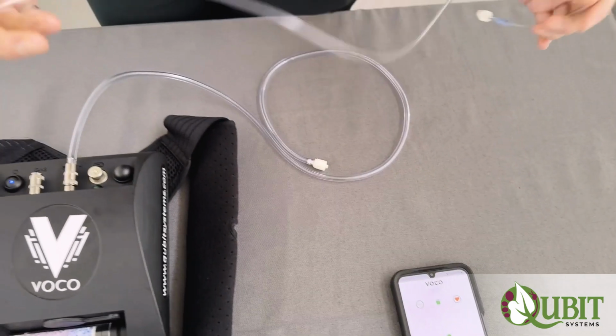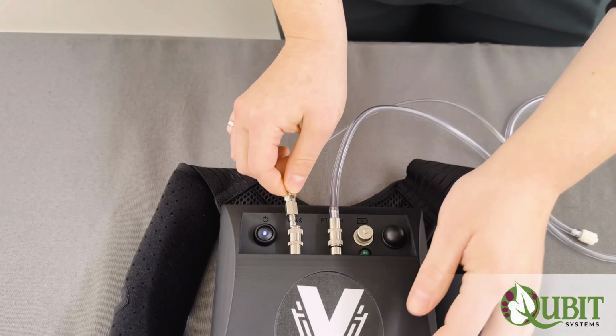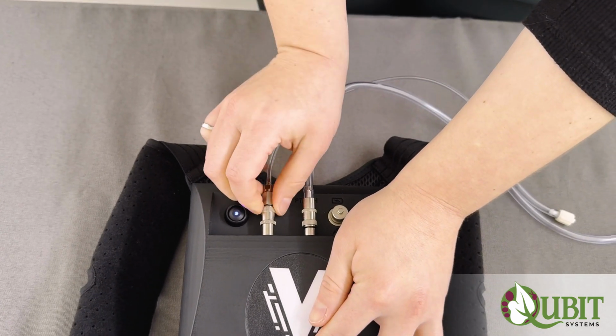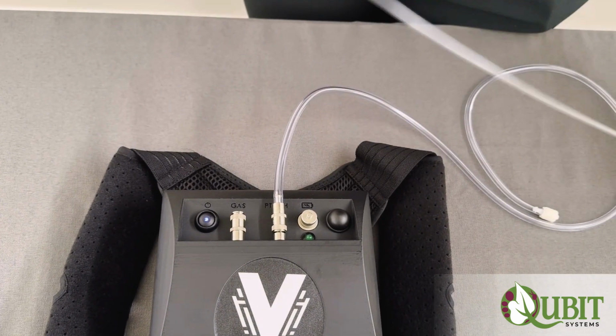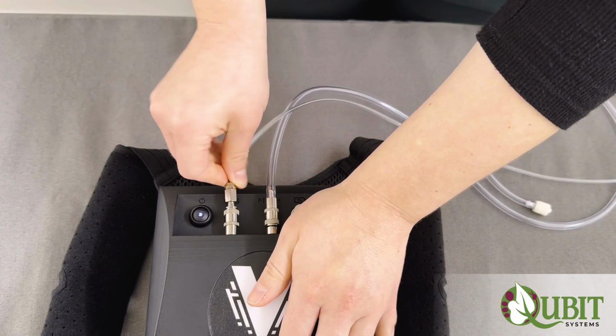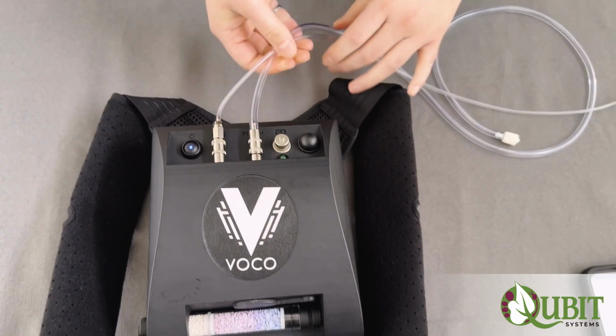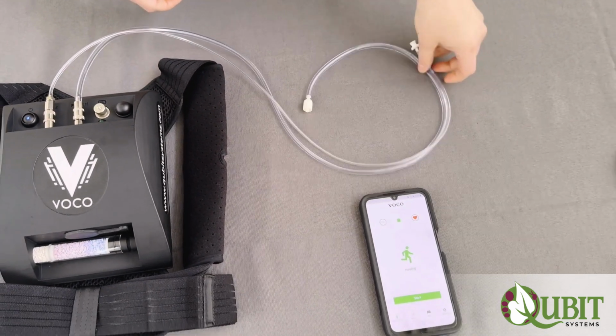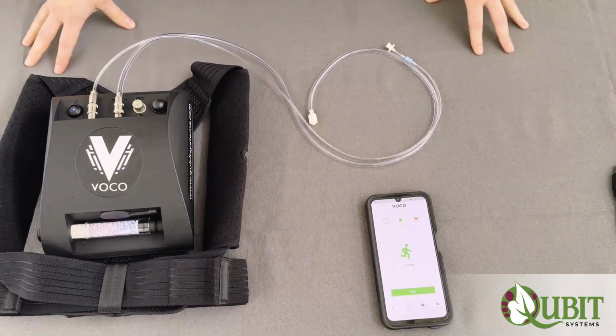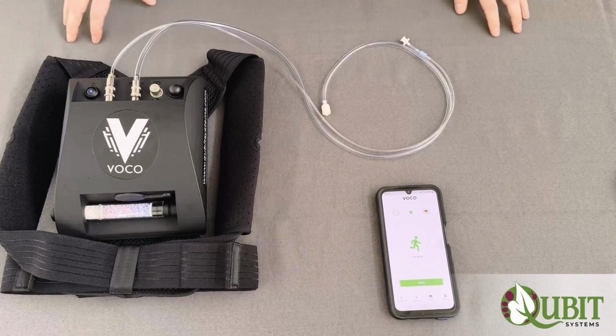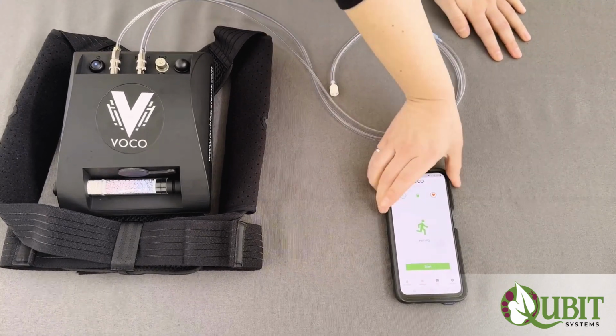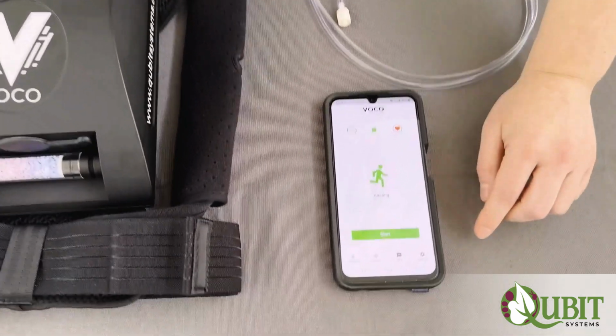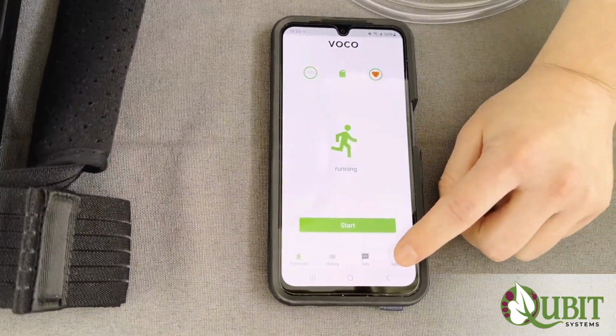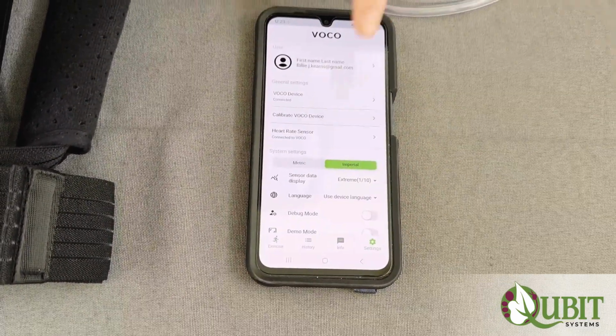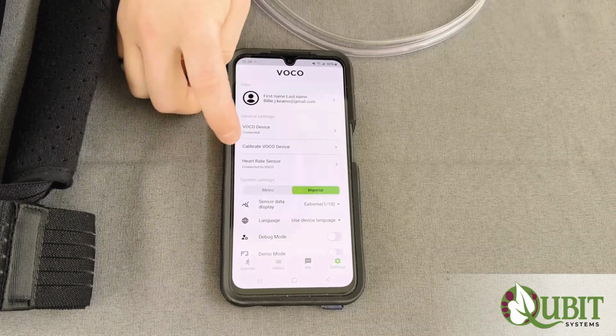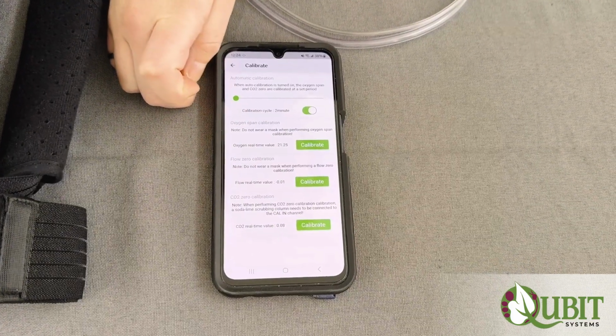Similarly for the gas tube, connect it to the gas port, simply push it in. To remove it, push down. It's good to hold on to the tube so it doesn't go flying. Push it in, and then let these vent. It's important not to calibrate while you are actively breathing through the VOCO. So on the VOCO app, to calibrate, go to Settings, and then go to Calibrate VOCO Device.